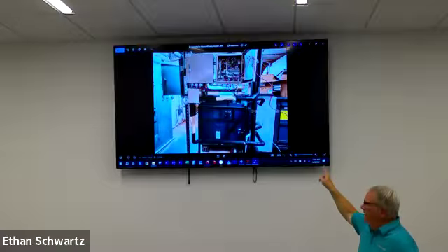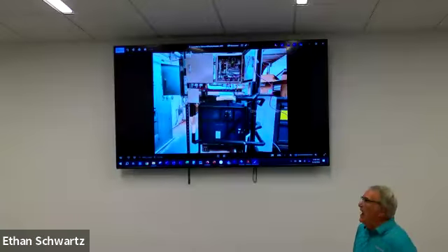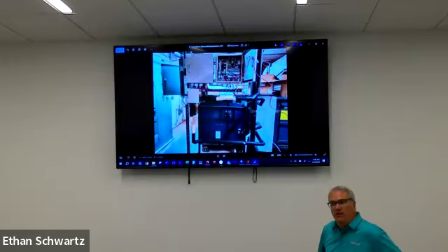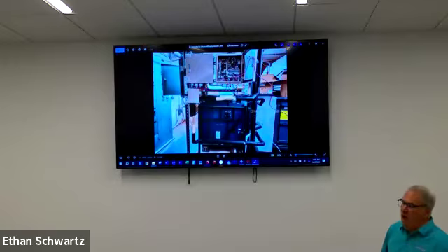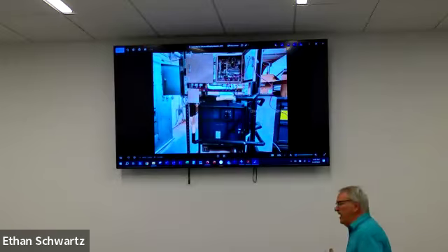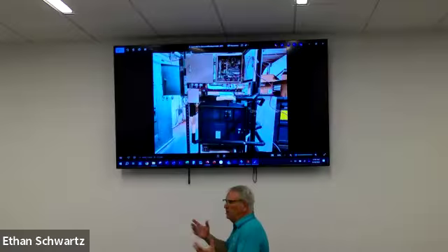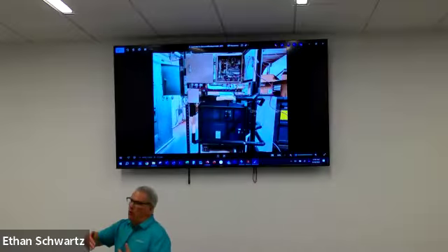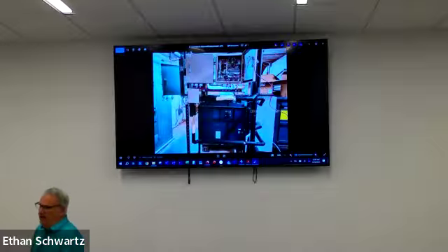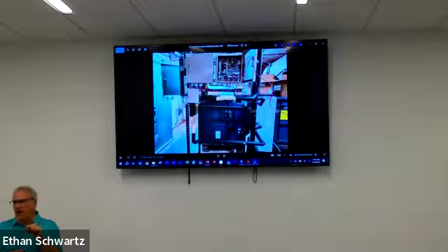outdoor air unit that will also modulate to create a supply air temperature. Now, Fujitsu does not have anything that, like on a DOAS system, even our outdoor air system, runs in relation to trying to maintain humidity or preheat. You don't have that. So these units are going to measure that return air or supply air temperature, and they're going to modulate to maintain that.